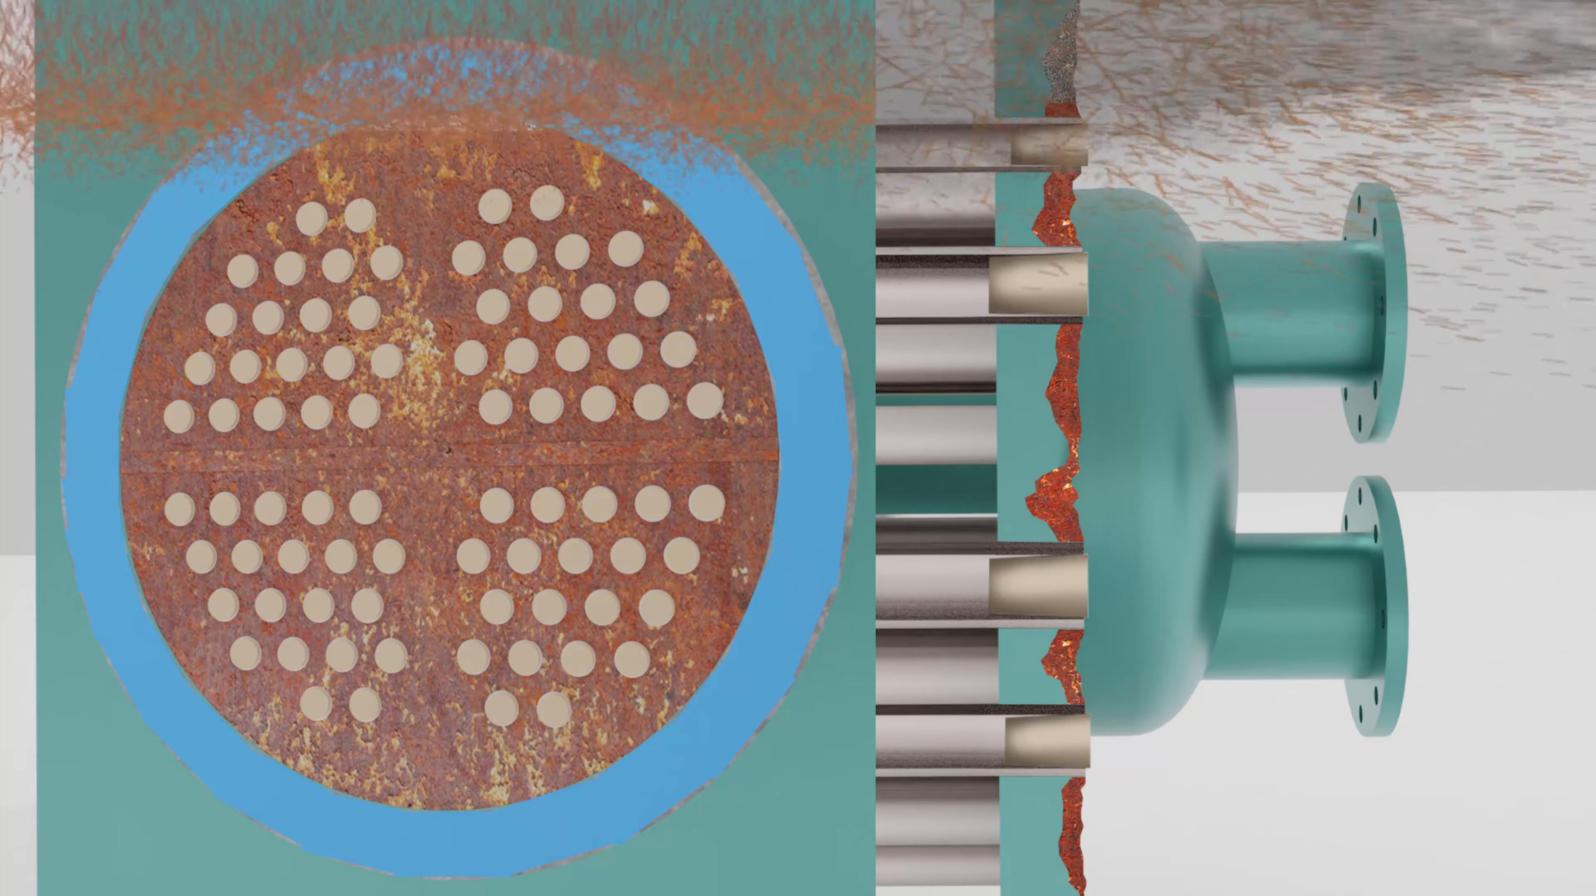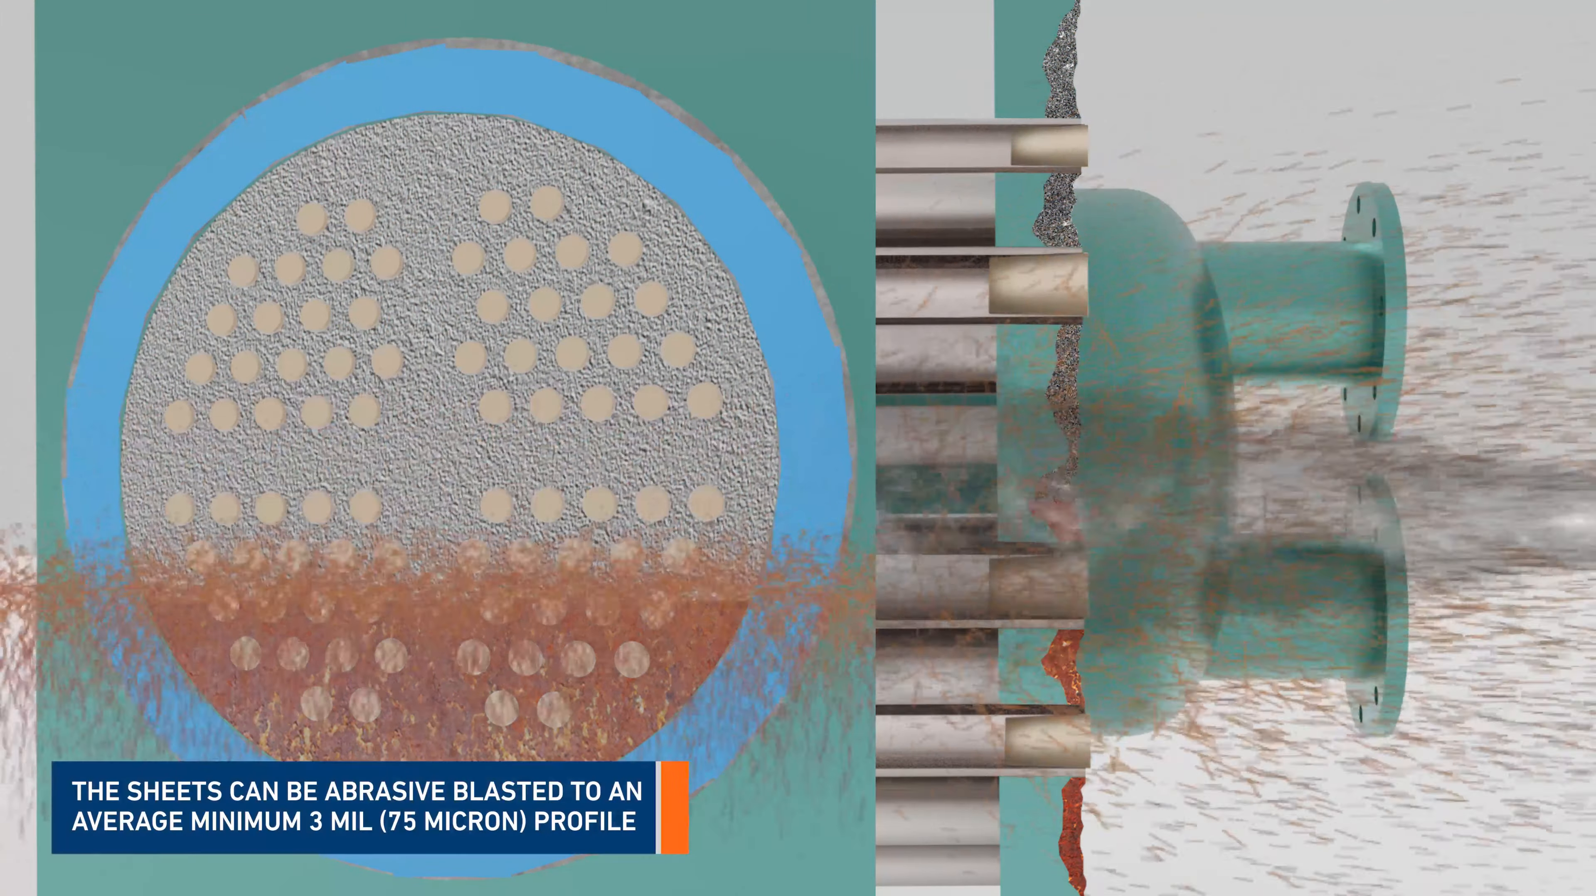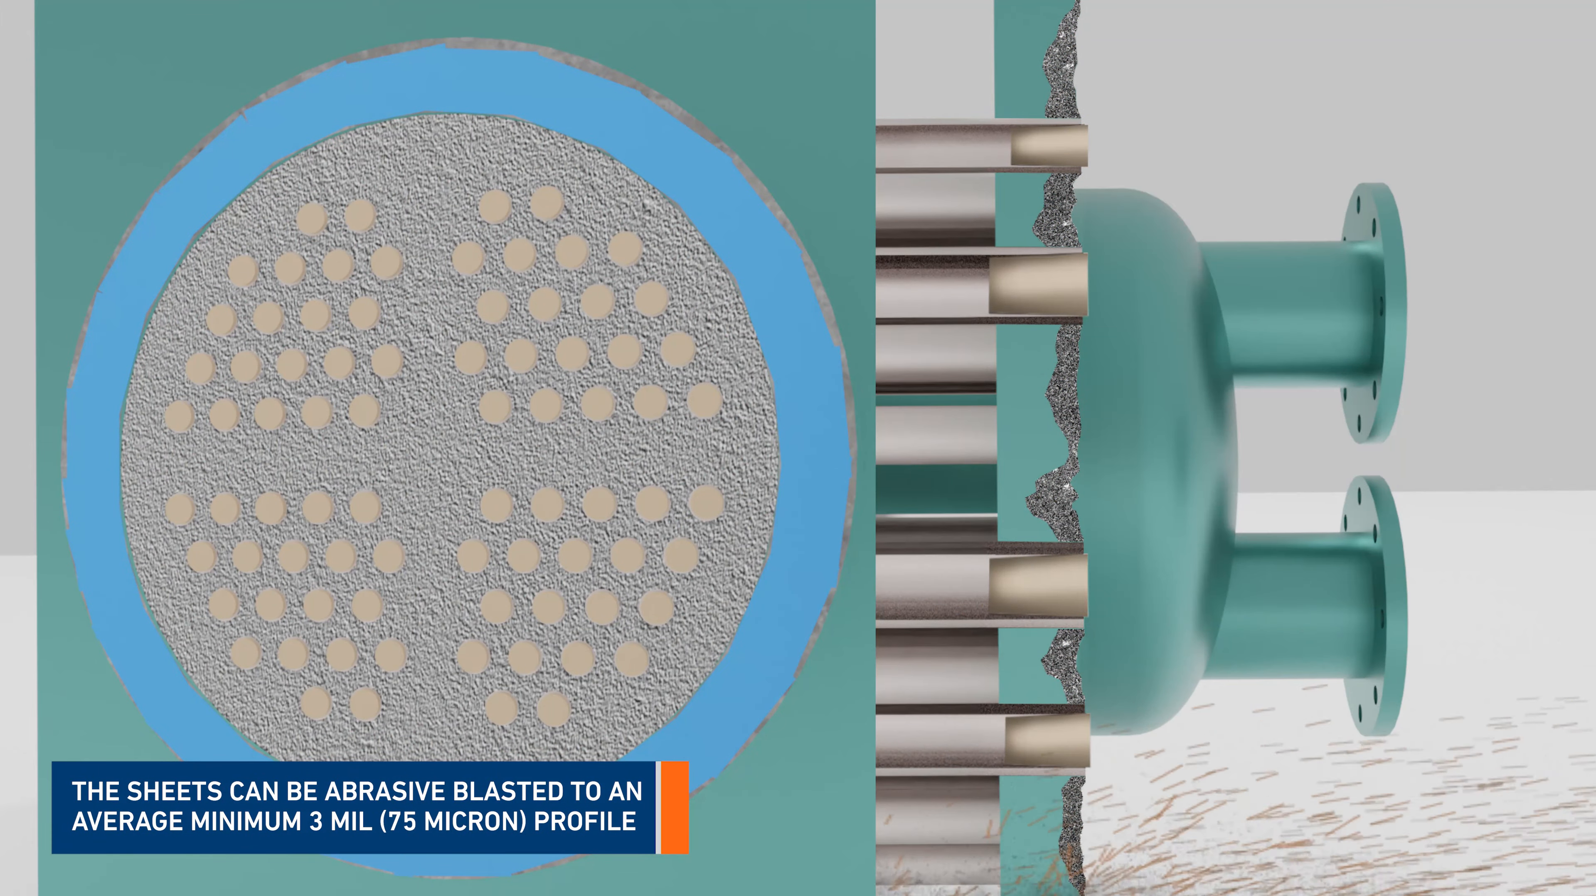Now that the tubes are protected, the sheets can be abrasive blasted to an average minimum of a 3 mil, 75 micron profile.